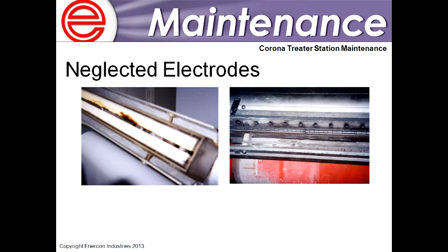You see two different samples. On the left there's a little bit of junk on the ceramic electrodes. On the right side, it shows where, with our design, you can hinge open the electrode assembly to access the cooling air ports when you're performing maintenance, and you can clean that out pretty nicely.